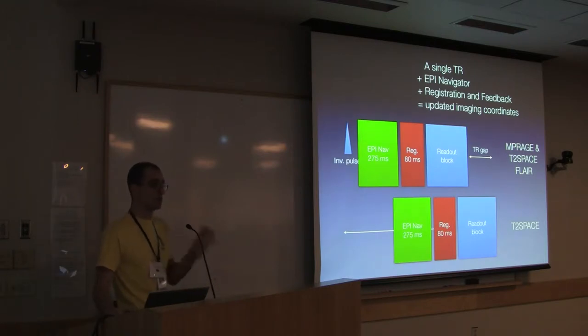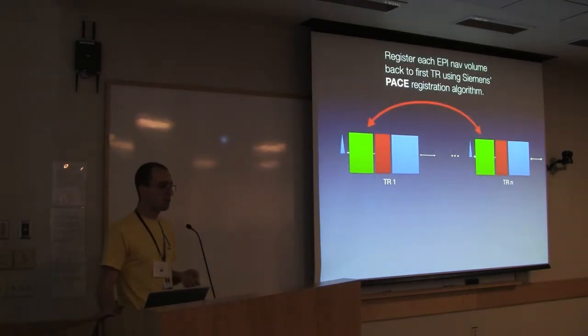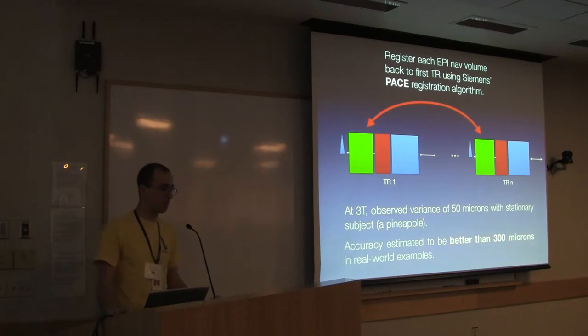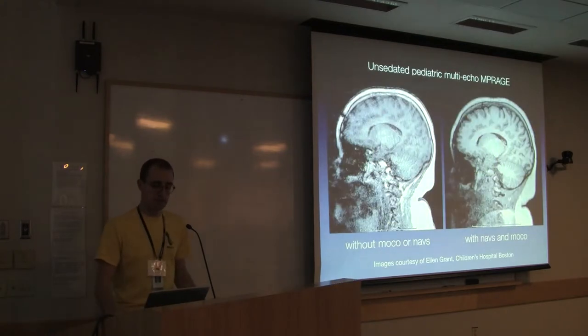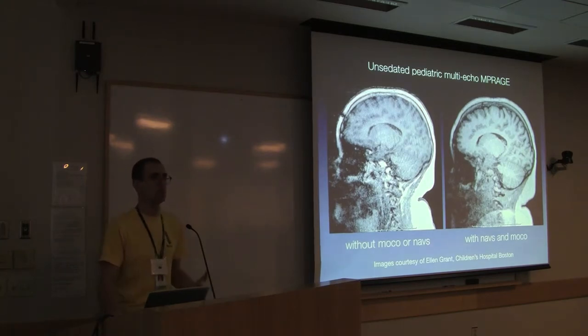I want to talk about how this works over multiple TRs. We know that the real MP-RAGE or T2 space sequences are made up of many, many repetitions of that pattern again and again. What we do is we register each EPI navigator that we get back to the first one we got at the beginning of the sequence. That way we're constantly imaging in the coordinates where we started at the beginning of the scan. We register them back actually using Siemens' Pace algorithm which some of you may be familiar with. At 3T we have observed a variance of only 50 microns with a stationary subject, a pineapple. I'm not going to promise that there isn't bias or other issues once the subject is actually moving. But we think that in real world examples we can probably get better than 300 micron accuracy.